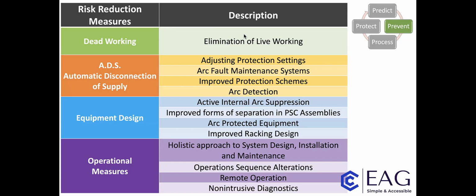It improves forms of separation in PSC assemblies, arc protected equipment, and improved racking design as well. Then operational measures: a holistic approach to system design, installation and maintenance, which I go into in some detail in the book. Operation sequence alterations, like paralleling transformers and things like that. Remote operation, I mentioned the distance and incident energy, and the more distance that you can put between you and a prospective arcing source, there is a massive reduction in incident energy. And then non-intrusive diagnostics as well, that's still within that point.